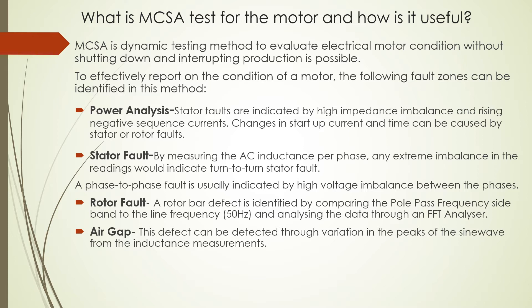A phase-to-phase fault is usually indicated by high voltage imbalance between the phases. Rotor fault: a rotor bar defect is identified by comparing the pole pass frequency sideband to the line frequency and analyzing the data through an FFT analyzer. Air gap: this defect can be detected through variation in the peaks of the sine wave from the inductance measurements.